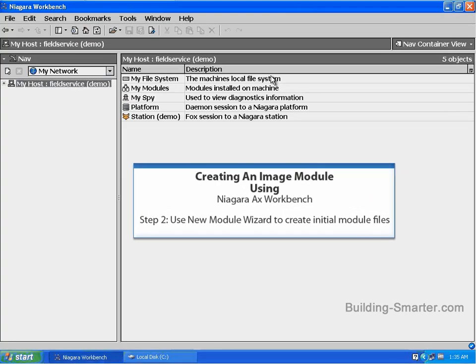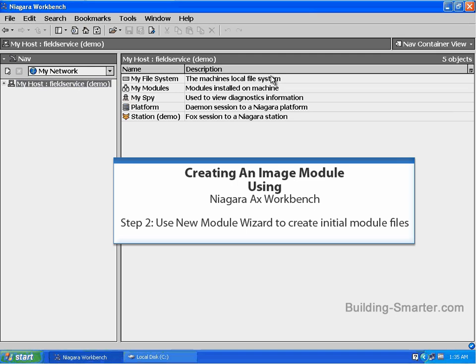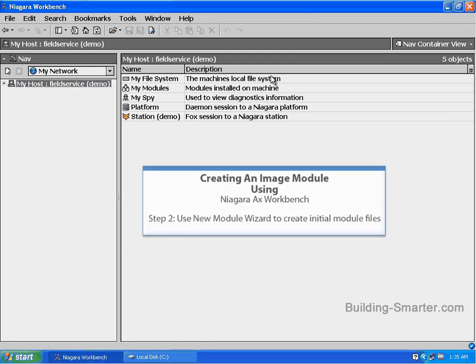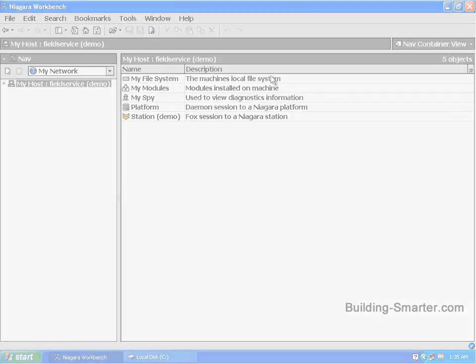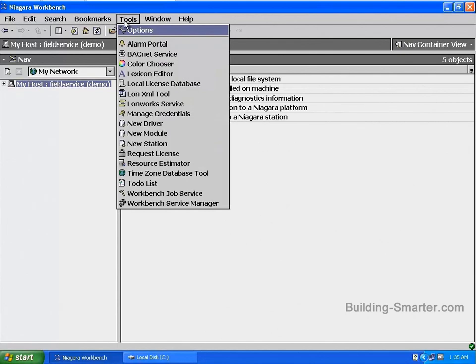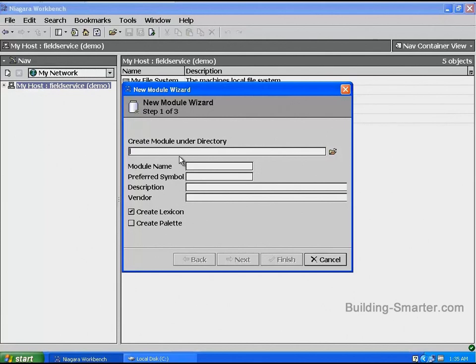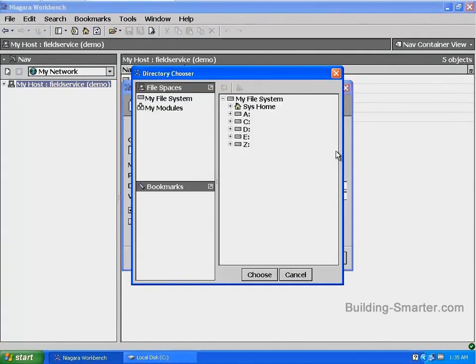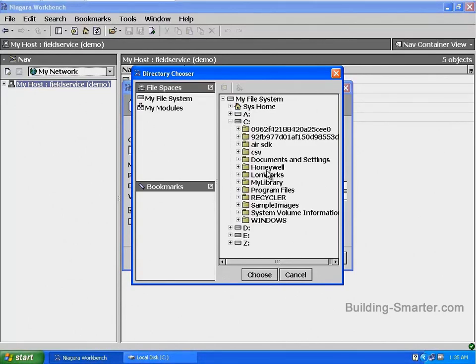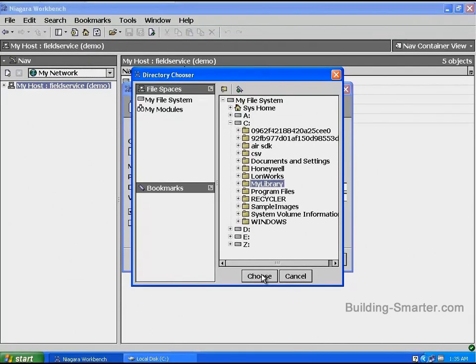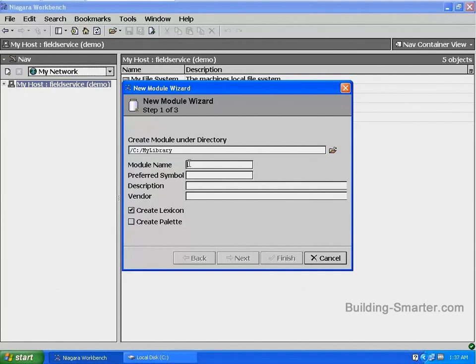Step 2, use the new module wizard to create the initial module files. In this step, we're going to use the Niagara AX Workbench new module wizard to create the initial files needed to create a module. We're going to create these files in the directory that we created in step 1. In the main toolbar under Tools, you'll find the new module wizard — select it. In the Create Module Under Directory dialog box, use the directory selector to choose the directory we created in step 1. Once you have selected my library, click the Choose button. In the Module Name dialog box, type in Sample Module. This will be the name of our module.